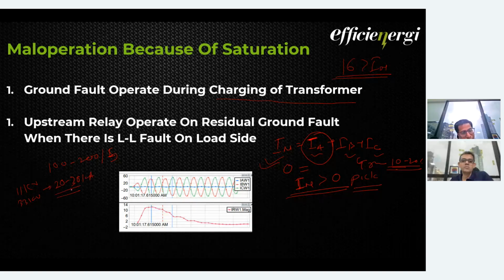So 20-30 kilo ampere, if you can see, and if you are using this 5P10 CT or 10 CTs. So 10, as I said, this is the ALF, that is accuracy limit factor. So up to 10 times of the primary, that is 10 times of the 100, you can see only 1000 ampere. So up to 1000 ampere, it can guarantee you a 5% error margin. But a fault of 20 kilo ampere, that is 200 times, not 20 times, 20,000, 200 times. If it goes, then it is expected that these CTs will heavily saturate, and this will not operate as intended.